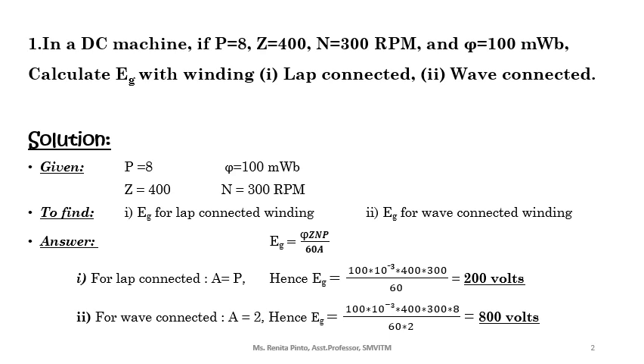We already know the generated EMF EG is given by EG = ΦZnP divided by 60A. The only difference when calculating generated EMF for lap connected versus wave connected is: for lap connected, A equals the number of poles P; whereas for wave connected, A equals 2. So substitute A = P and A = 2 in the main equation.